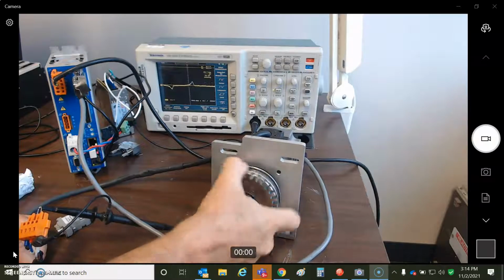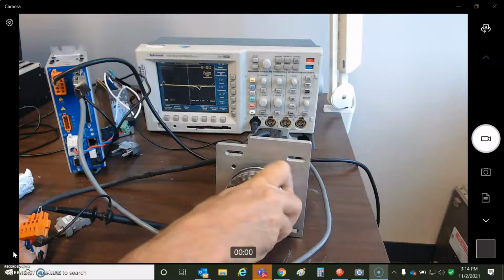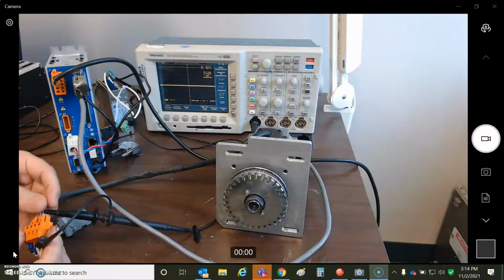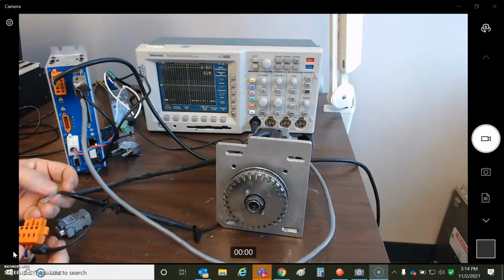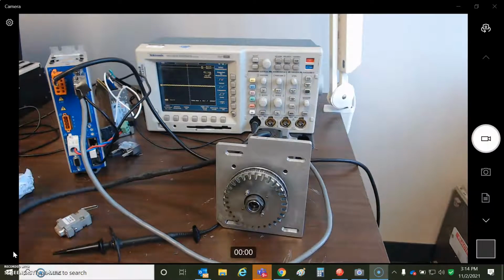So if I made 50 volts and 1 ohm, I'd have 50 amps. So it's kind of hard to generate that much. I'd have to spin it really fast to burn up the motor winding or demag the motor. So shorting the motor is not always a good idea. Maybe there should be some resistance or control of the current. So we'll take a look at how the drive does dynamic braking.